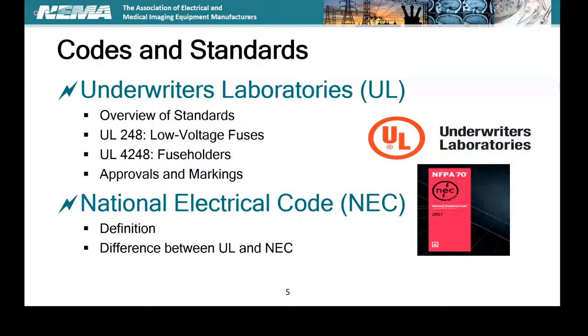So just as an FYI, if you look on that list, whether it's UL or anybody else, and it's not there, check and see if any other NRTLs have been accredited to that standard. And if nobody has, you may ask that NRTL to show you that they've at least submitted to OSHA for accreditation. Good point. Good point.